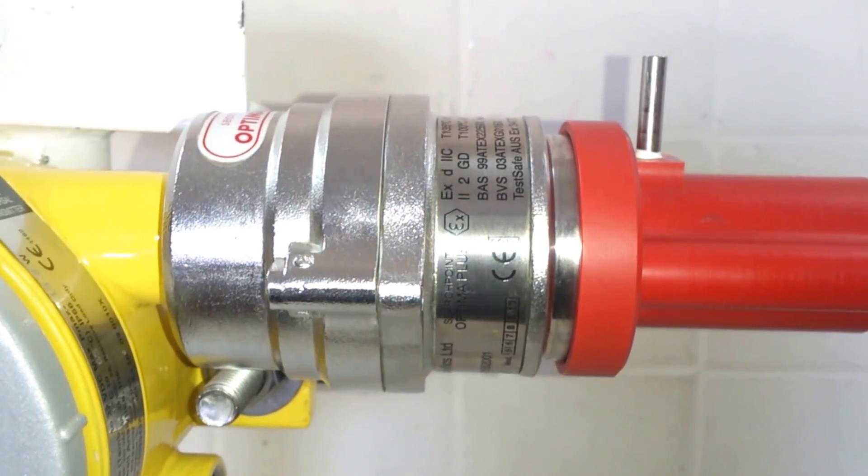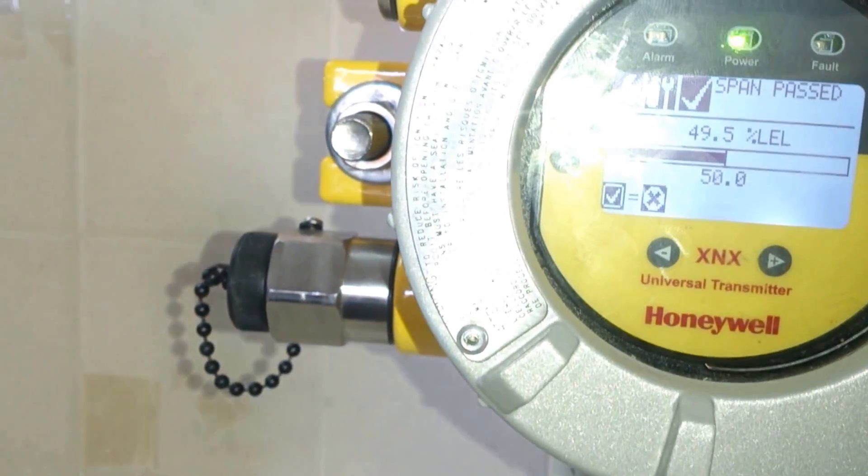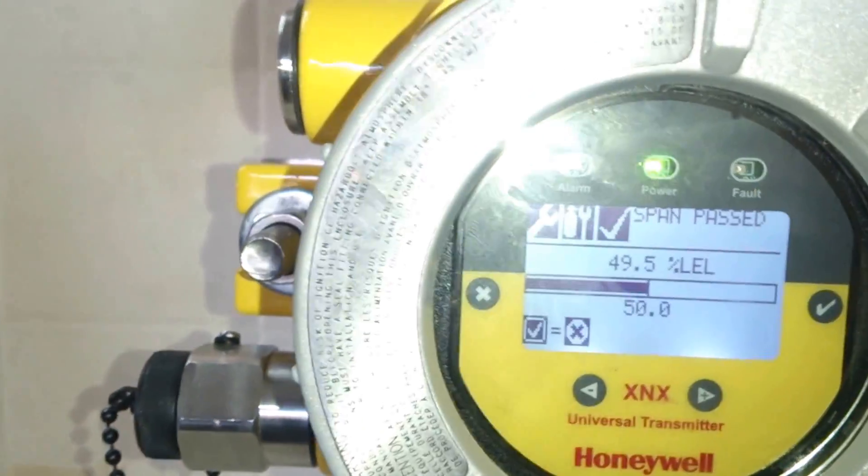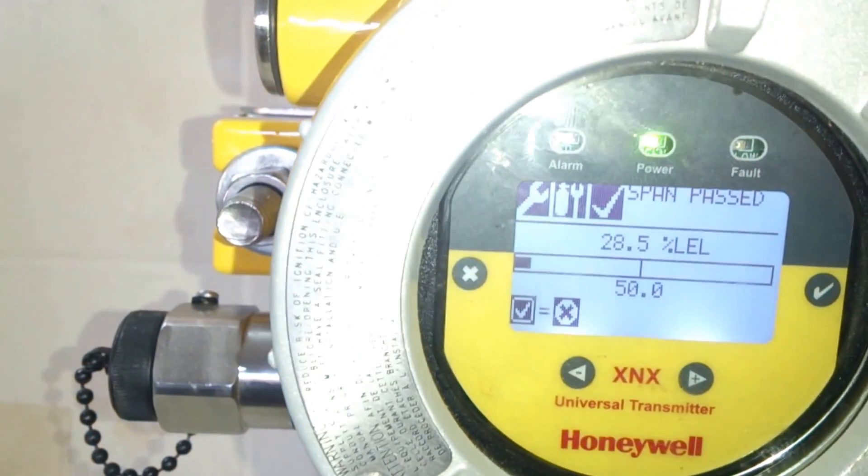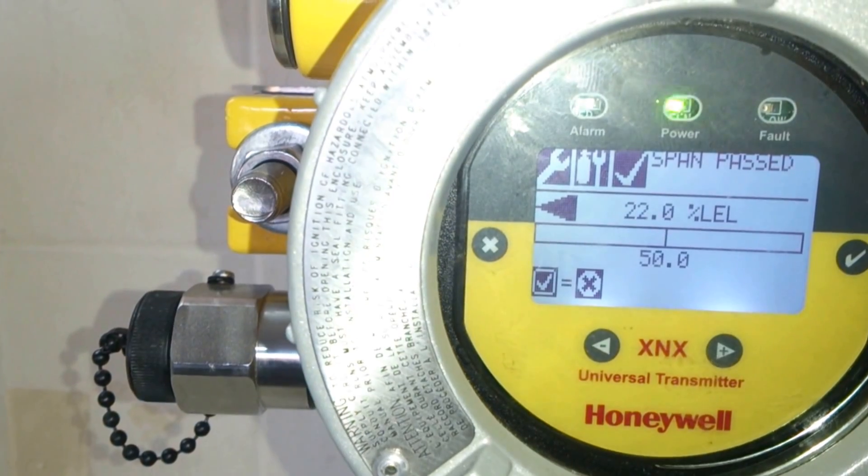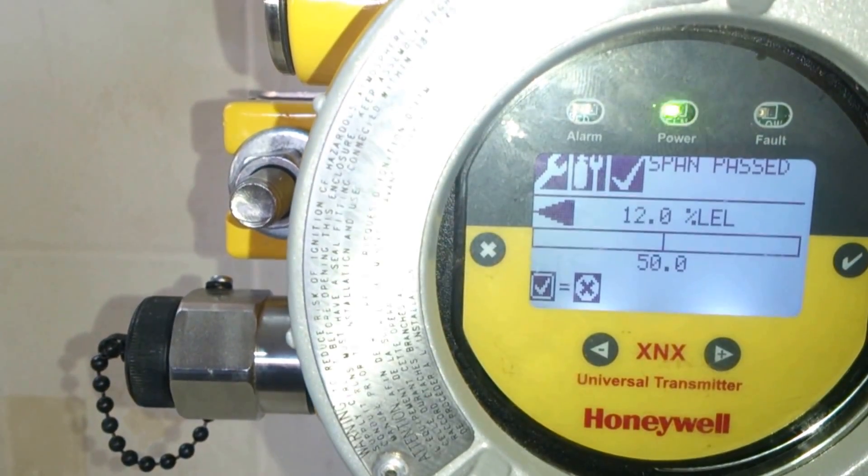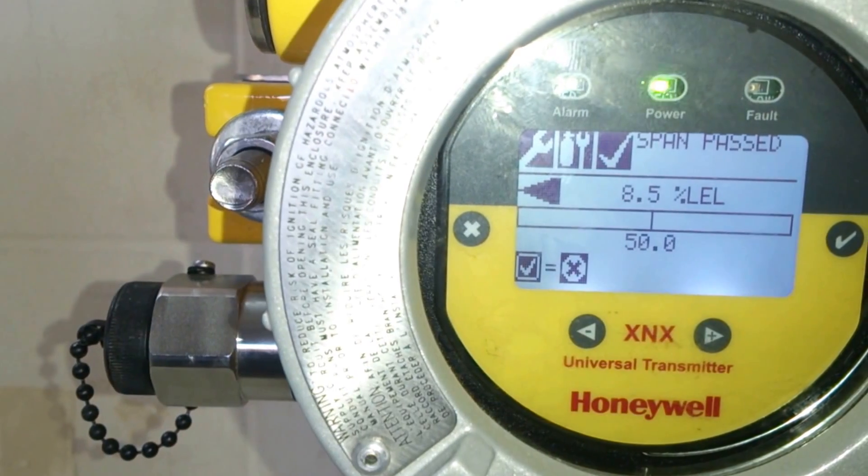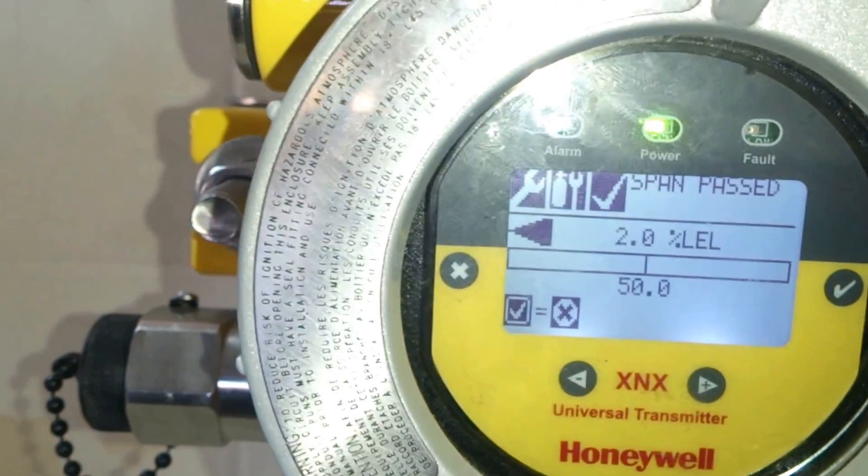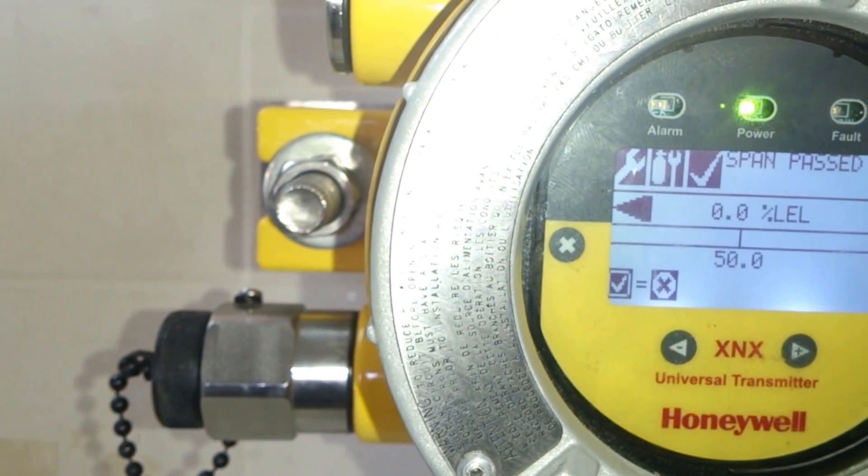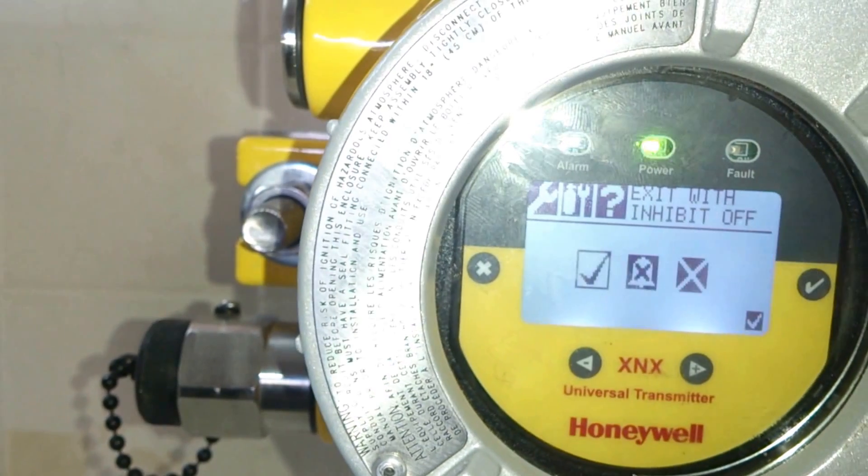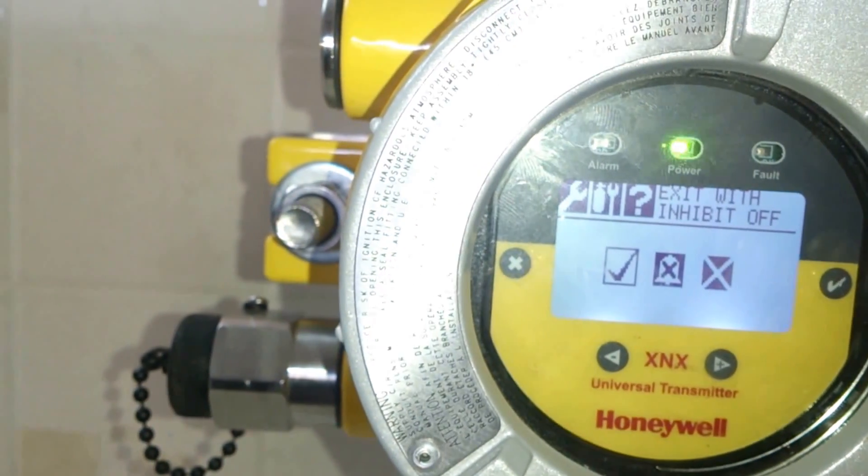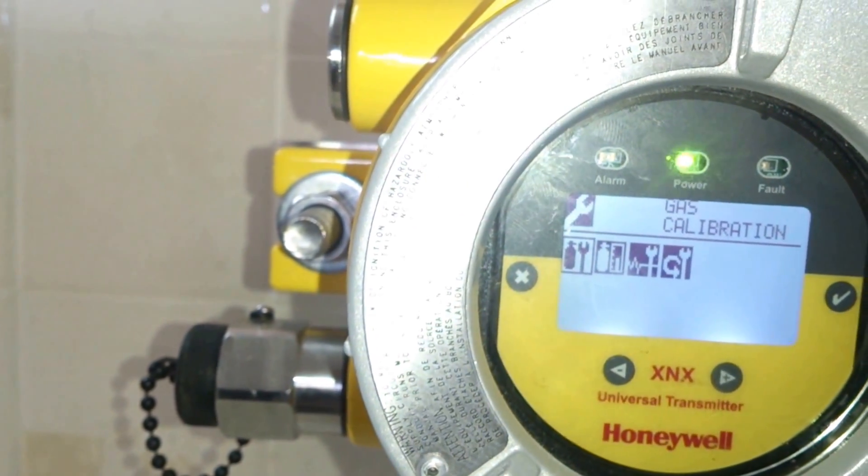The calibration cap is still connected. Now you can see the span is passed, i.e. the span calibration is accepted. Now we remove the calibration cap. Now wait for a stable value of the span until it reaches 0. Once it reaches 0, we save it and select exit with inhibit off for calibration purpose.